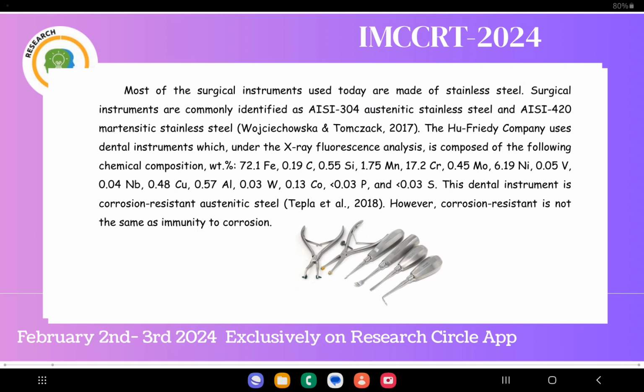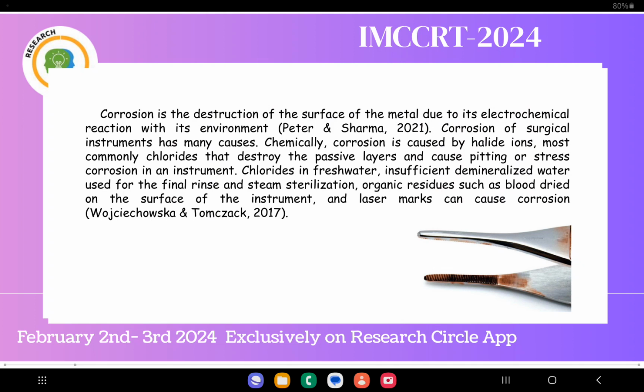This dental instrument is corrosion resistant austenitic steel. However, corrosion resistant is not the same as immunity to corrosion. Corrosion is the destruction of the surface of the metal due to its electrochemical reaction with its environment. Corrosion of surgical instruments has many causes. Chemically, corrosion is caused by halide ions, most commonly chlorides, that destroy the passive layers and cause pitting or stress corrosion in an instrument. Chlorides in fresh water, insufficient demineralized water used for the final rinse and steam sterilization, organic residues such as blood dried on the surface of the instrument, and laser marks can cause corrosion.